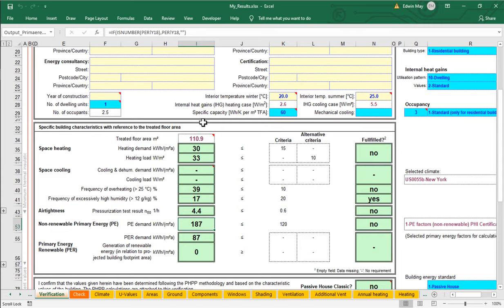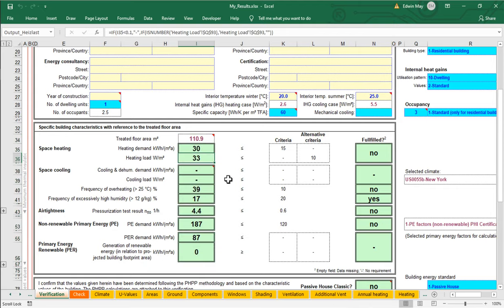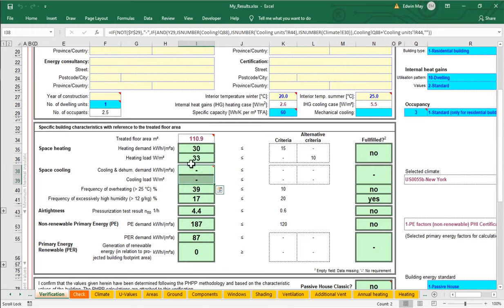Let's talk about cooling. When it comes to my annual energy performance results down here in column I, notice that I'm getting some good results for heating demand, peak heating load, primary energy, and primary energy renewable. But notice here that I'm not getting any values for cooling and dehumidification energy demand, peak cooling, or peak cooling load. Notice though that I am getting some interesting results for frequency of overheating — that is, percentage of hours above 25 degrees Celsius, 77 degrees Fahrenheit — and frequency of excess high humidity above 12 grams per kilogram, that's like 60% RH at 77 degrees.